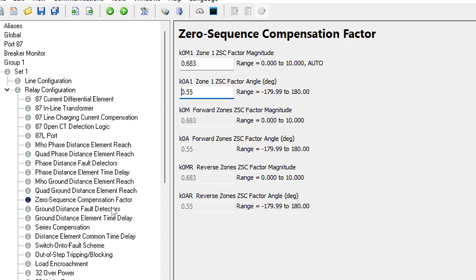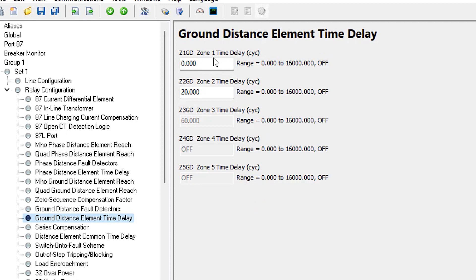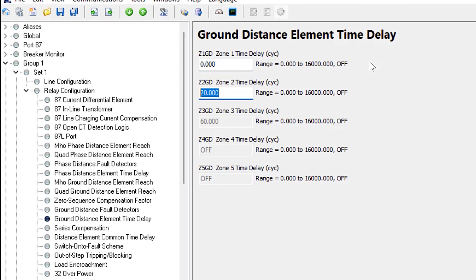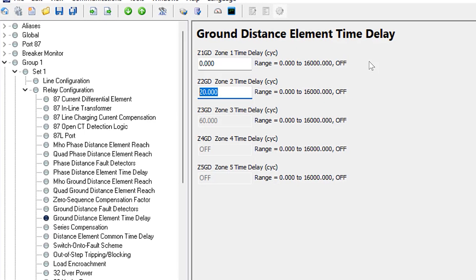The last thing to set is the time delays for the ground distance elements. Zone one delay is set to instantaneous (zero cycles) since it's set to 80% underreach. Zone two is set to 30 cycles to coordinate with protection at the remote substation, since that element reaches 120% and will see faults at the remote bus. Now the mho ground distance element is fully programmed.